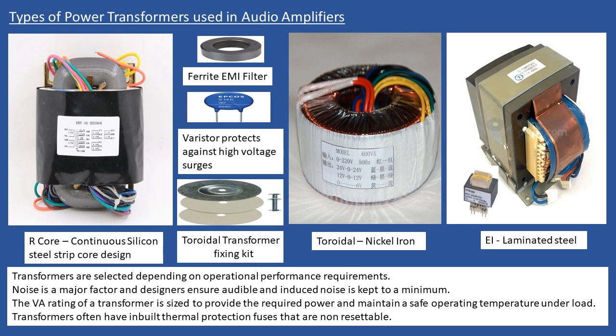And you would also find these varistors in switch mode power supplies, very, very common. And just be aware that if you had an issue which looked as if you had an issue with a power transformer, you have to check if you have a circuit with varistors in, and make sure that that varistor hasn't shorted.